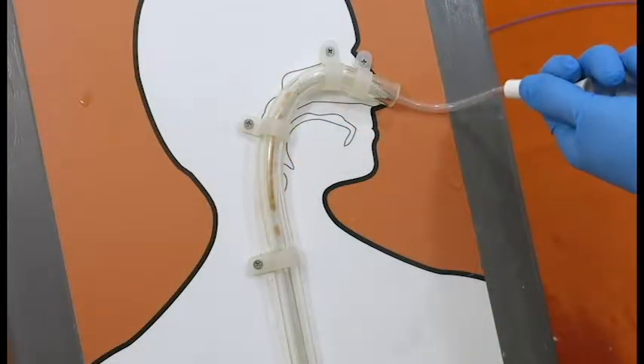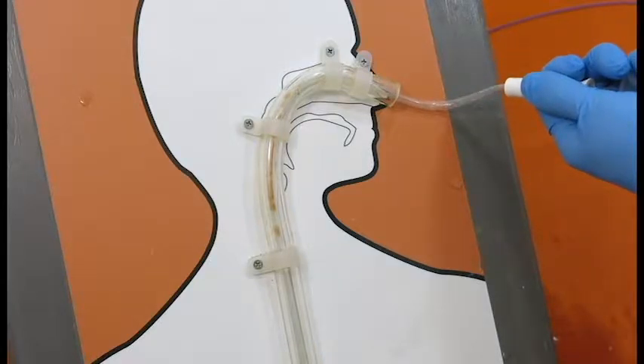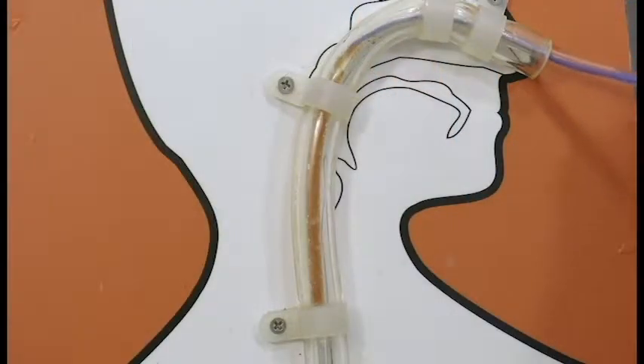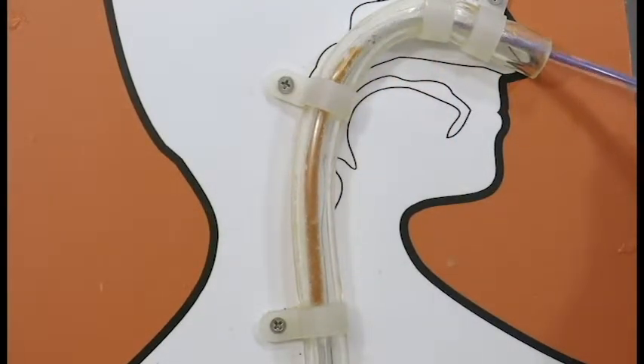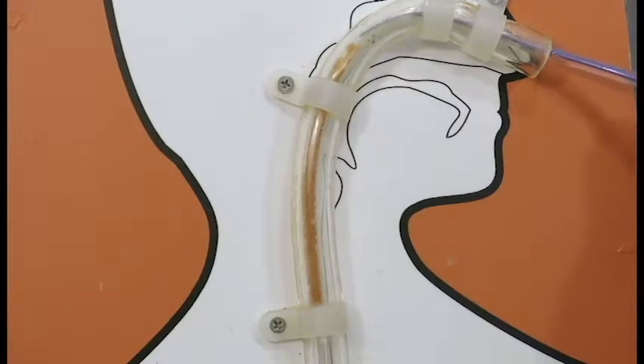Viscous clogs, such as those consisting of formula and fiber, require more water flushing and aspiration than dry hard clogs. The TubeClear operator may feel the clearing stem slow as it advances, rather than meeting a more solid resistance.